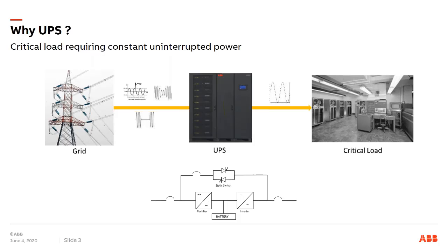So the inverter will have DC power, whether there's DC power coming from the utility via the rectifier or not. If utility power fails, the inverter will just take DC power from the battery and continue to support uninterrupted power as long as there's energy on the battery, or until the rectifier kicks in again.